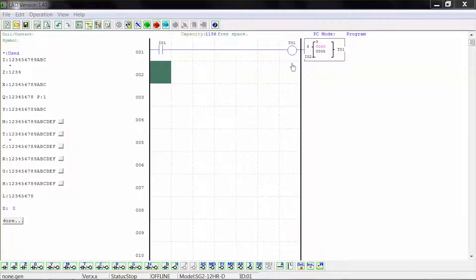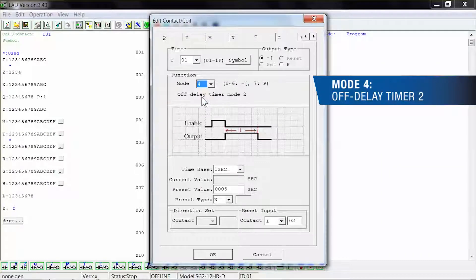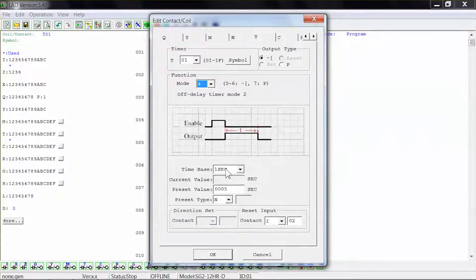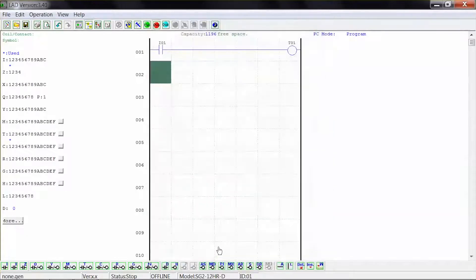For the next example, double click the timing coil to open the edit coil window. Select mode 4, which is an off-delay timer version 2. Select your time base for 1 second, your preset value for 5 seconds shown as 0005, and your preset type for N which is numeric constant. And select your reset input for contact I02. Close the window by clicking OK and click run to start the simulation.